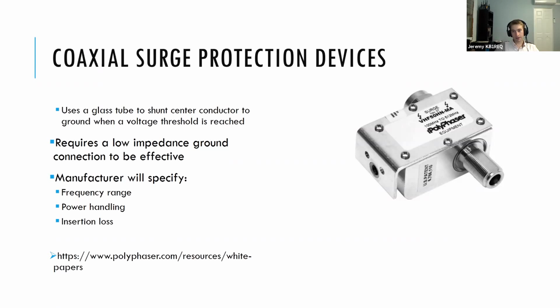So, a surge protector does a lot to prevent a surge flowing in directly on the center conductor, but there is still going to be some residual current downstream from this, and that's why it's important to make sure that you still have grounding on that equipment. This is not a substitute for a full air gap from the equipment.